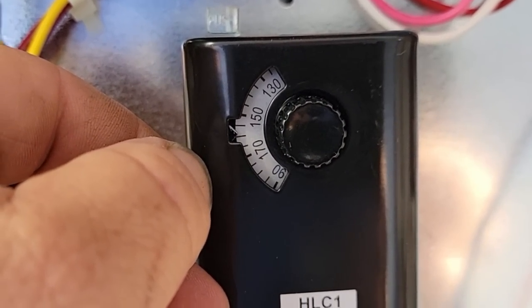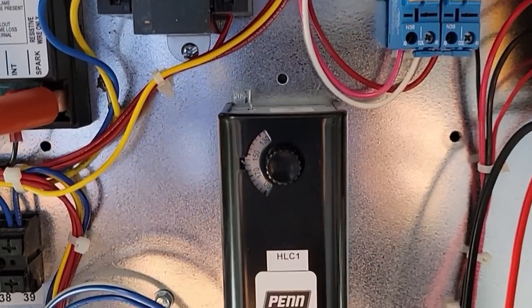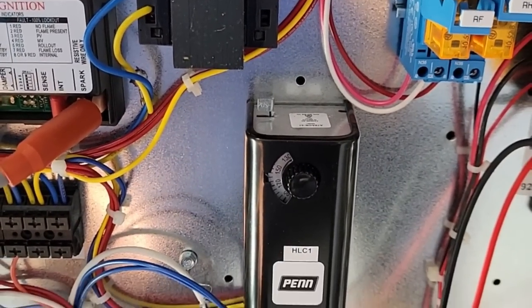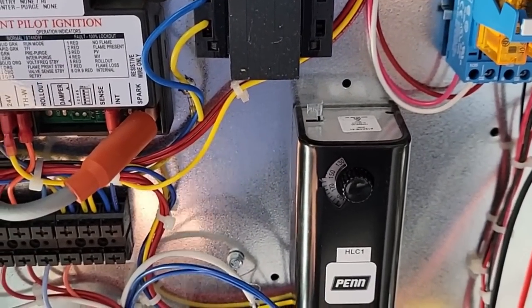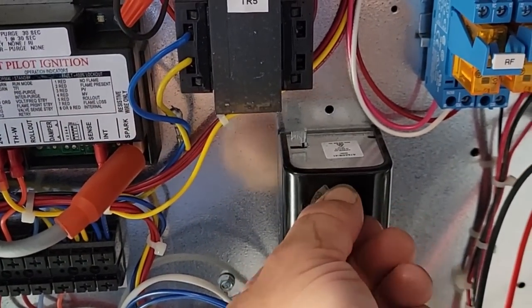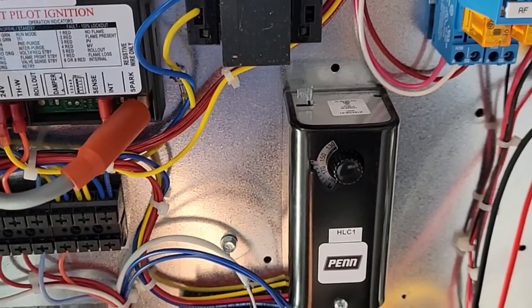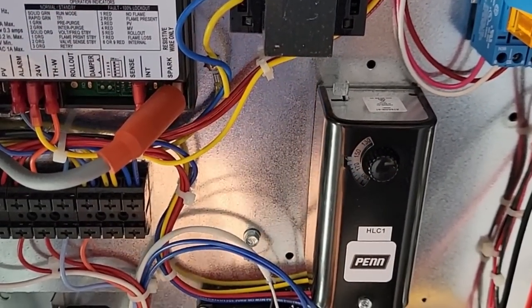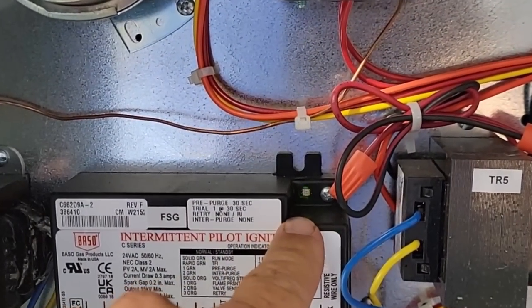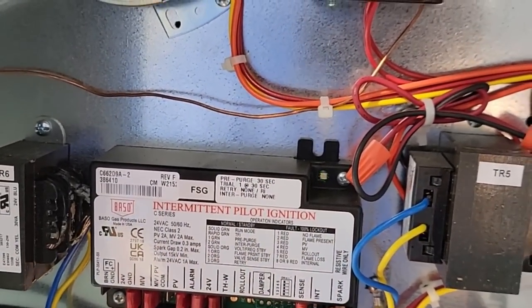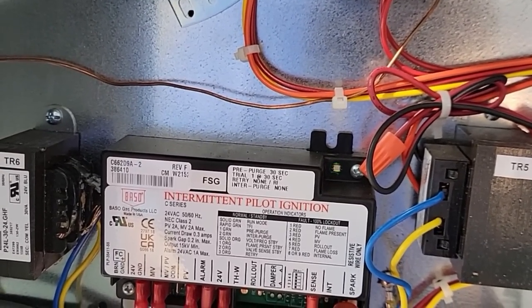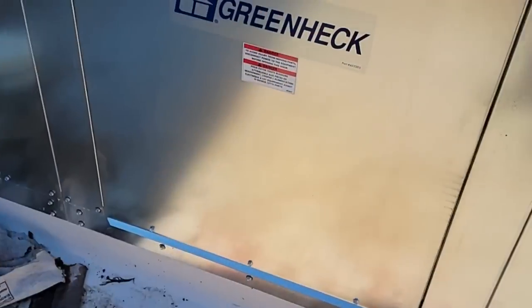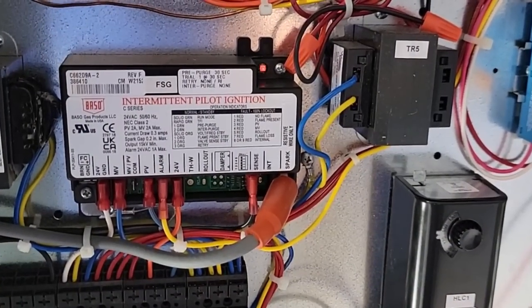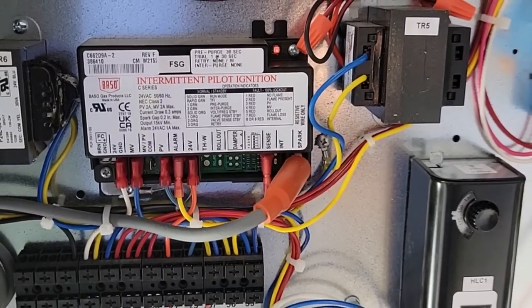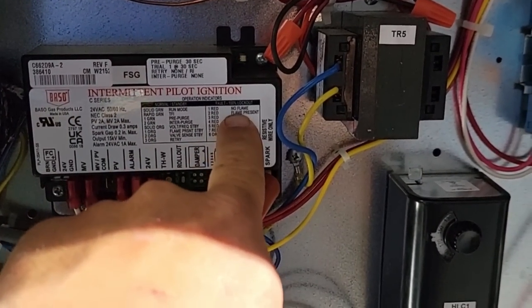160 area is about as high as you can get it, which any residual heat probably be good to have. Nothing's gonna catch on fire at 160, so we're just gonna leave that at max. It actually stops there. It could go higher, but they've gotta stop, so we're gonna leave it at that. There's the ignition blinking. Just heard a click. And we might have a burner. Yeah, we can see it right here. We have a blinking red, which is no flame.